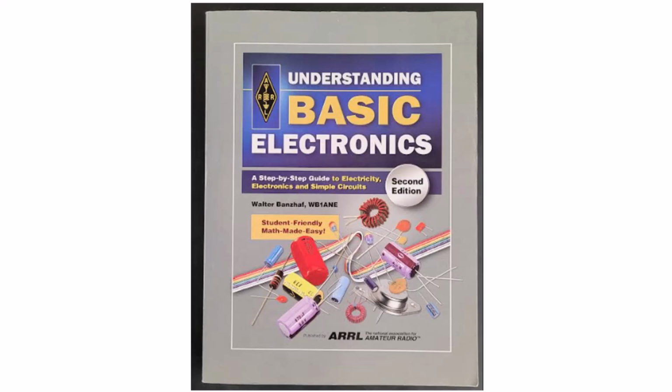First question asks, what is the minimum allowable discharge voltage for maximum life of a standard 12-volt lead-acid battery? And the answer is 10.5 volts. If you discharge below that level, it can cause changes in the chemical nature of the lead-acid cell, which is not reversible. So it will damage and destroy the cell.